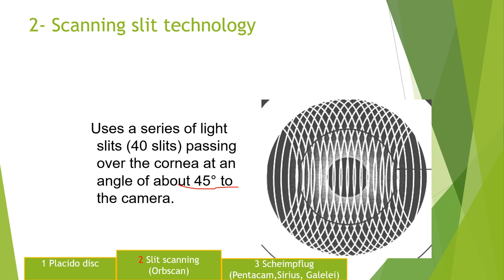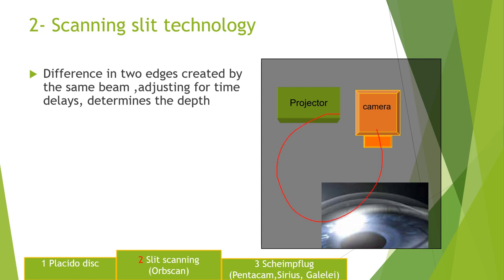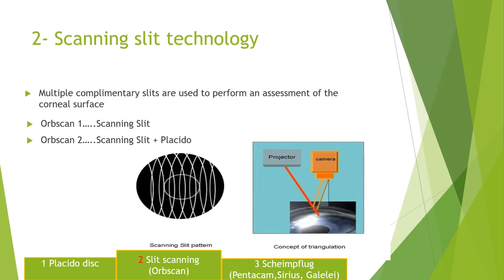How does it measure the elevation? You have a projector, and there is one reflection from the anterior corneal surface and one reflection from the posterior corneal surface. The difference between the two reflections is the depth of the cornea or the pachymetry, and from there the data is acquired. In the Orbscan we use scanning slit technology, and that is the only machine in the market which uses the scanning slit technology.